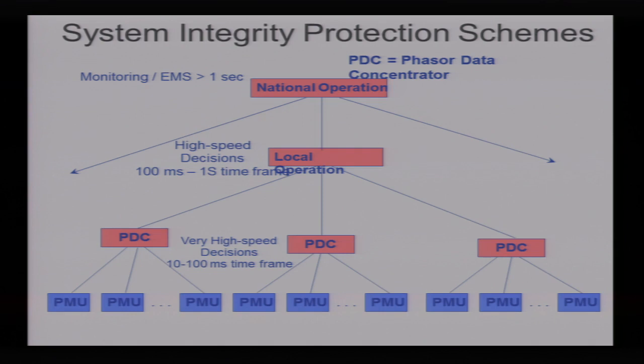As we look to the future, there are going to be new applications of these measurements. For example, if I look over a wide area and start to see the angle between two areas, like I saw up in Cleveland before, getting way, way too large, I can declare a dynamic out-of-step condition and actually trip off and break the system in half to prevent both systems from knocking one another apart. This means I'll need to communicate between PMUs - by the way, PMU stands for phasor measurement unit.